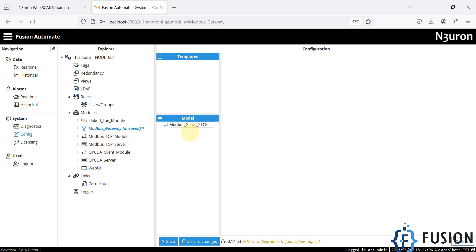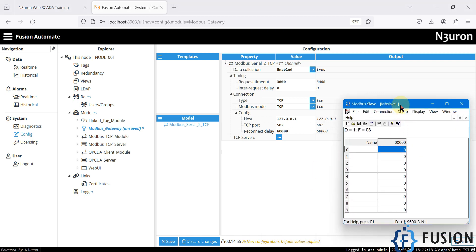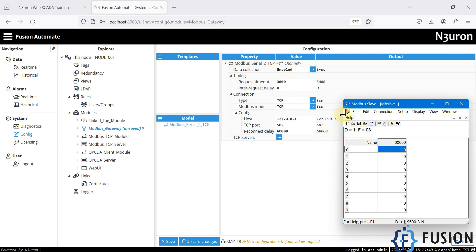We will create a Modbus serial to TCP channel. Right now you can see on screen that we have Modbus slave software acting as a Modbus serial device. It is connected on COM port 1 with 9600 baud rate, data bits 8, parity none, and stop bit 1. We are going to collect the data from this device and deliver it on the Modbus TCP protocol, then launch multiple instances of a Modbus client application.